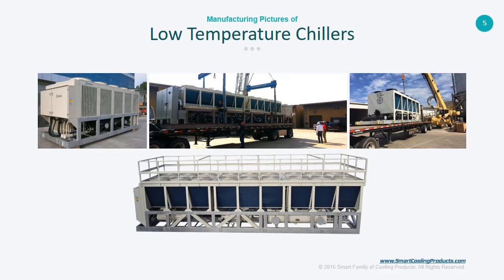Moving on to some of the pictures here of some low temp chillers we've done in the past. The top left there was a unit that was cooling Dynalene from 8 degrees down to 0. The unit in the middle there was a rental chiller. This one actually is quite unique. It was capable of operating in ambients from -20 up to 100-degree ambient, and could operate as low as -30 leaving fluid temperature. That's a wide range that we were able to supply in that one unit, and it fit perfectly with this customer's rental applications.